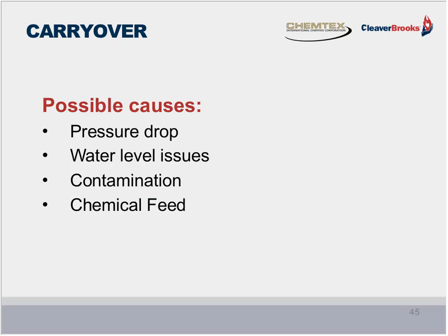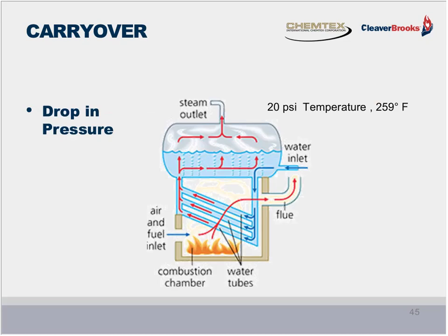While working for Betz, a study was done in which 1,000 incidents of carryover were studied in the field. Of this study, 95% were proven to be caused by mechanical problems. While chemical control is important, and it can and will cause and contribute to carryover, it's not always the problem.